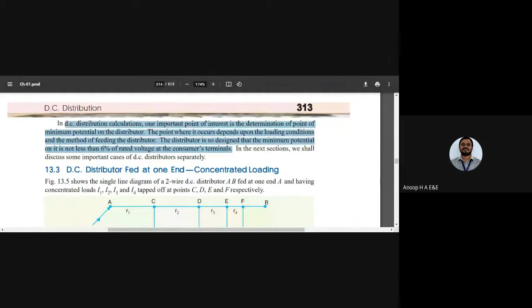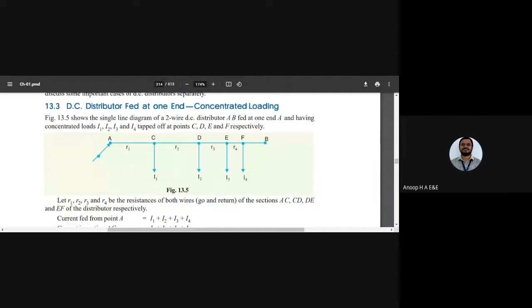In calculations, you need to note down the minimum potential of the distributor. Next, you have the point at which the loading conditions will differ and the method of feeding the distributor. Next, the distributor is designed such that the minimum potential is not less than 6% of the rated voltage at the consumer terminals. All these are important things to keep in mind in a DC distribution calculation. Let's move on to the first type. We'll discuss only this part today, and I'm going to give a problem which you need to analyze and solve.